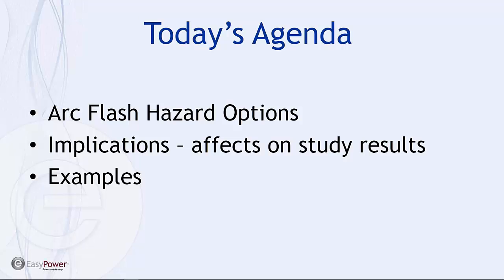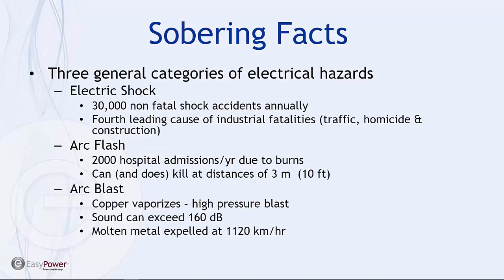So there can be significant learning and training about arc flash and what I refer to as the arc flash phenomena that will benefit the team members, specifically the qualified workers whose very safety relies on the correctness of the results of the study. So there's a self-feeding improvement cycle there, the more that the maintenance people are involved, not only in data collection, but in modeling the system.